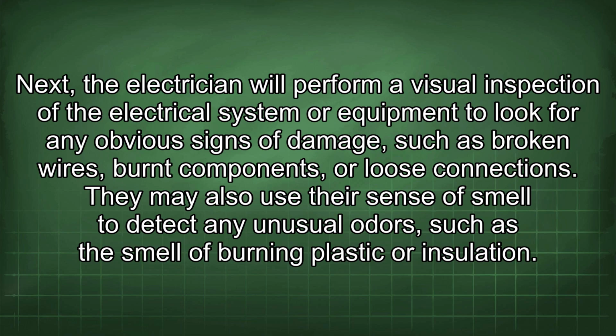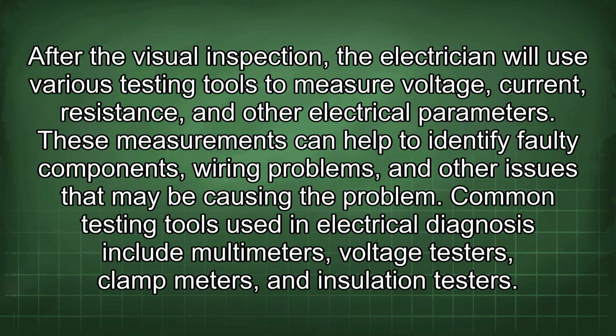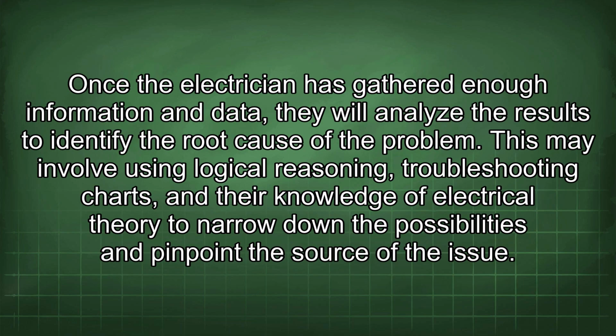or insulation. After the visual inspection, the electrician will use various testing tools to measure voltage, current, resistance, and other electrical parameters. These measurements can help to identify faulty components, wiring problems, and other issues that may be causing the problem. Common testing tools used in electrical diagnosis include multimeters, voltage testers, clamp meters, and insulation testers. Once the electrician has gathered enough information and data, they will analyze the results to identify the root cause of the problem.